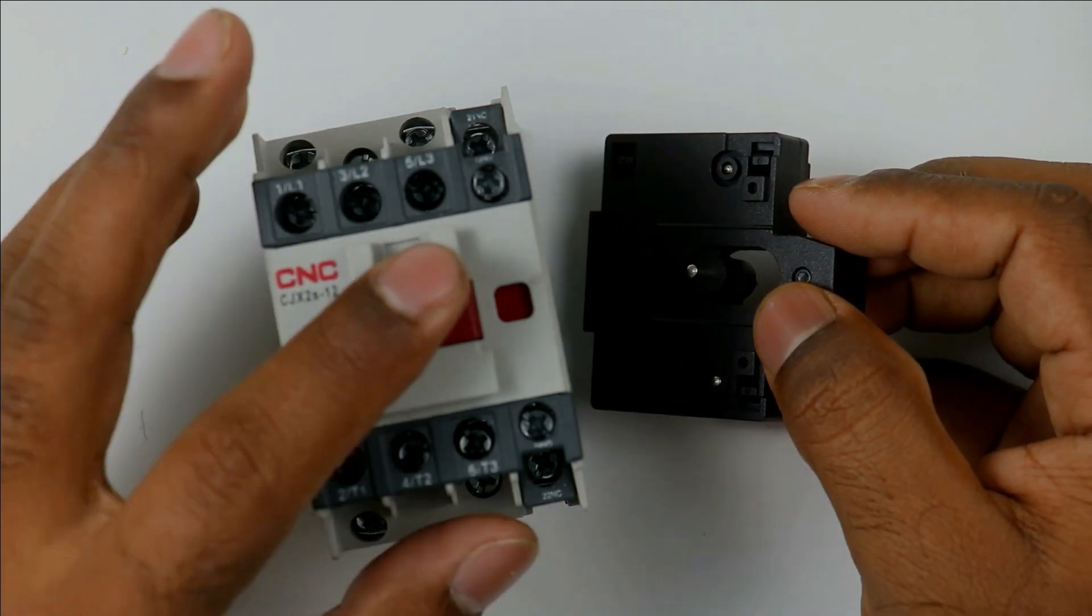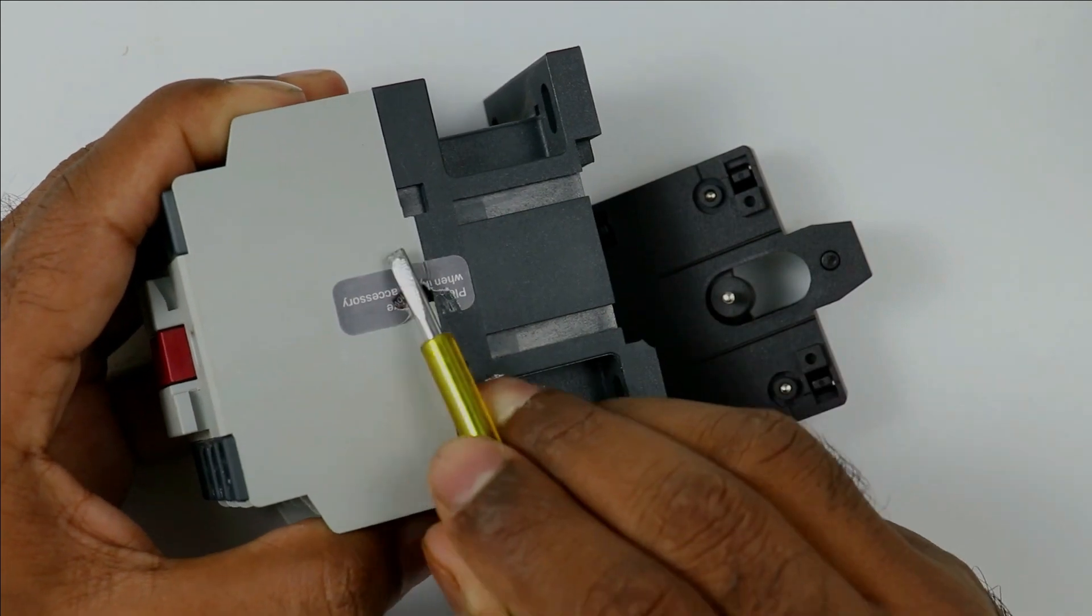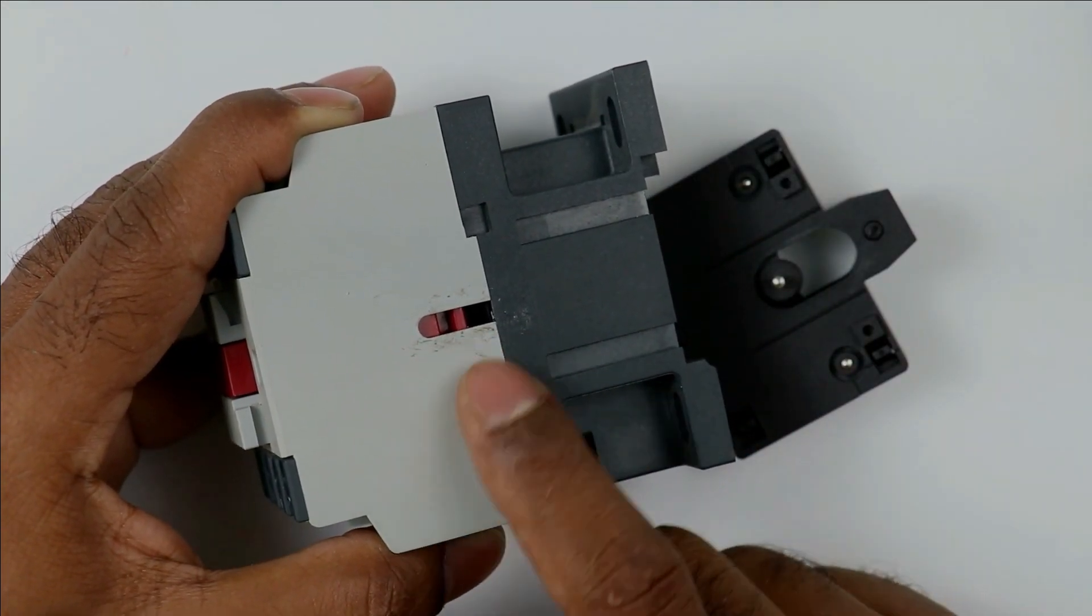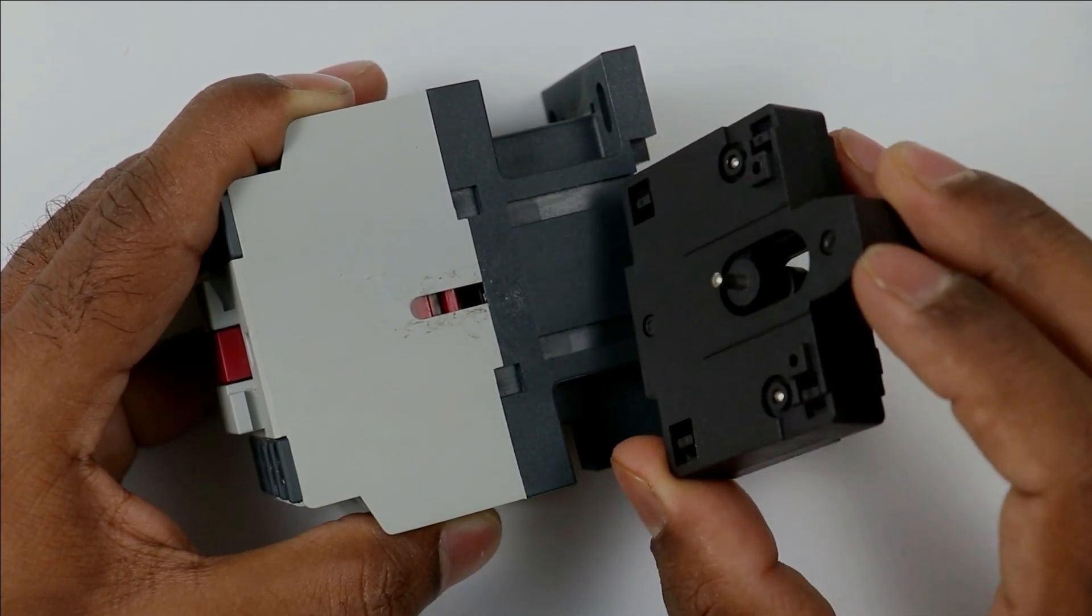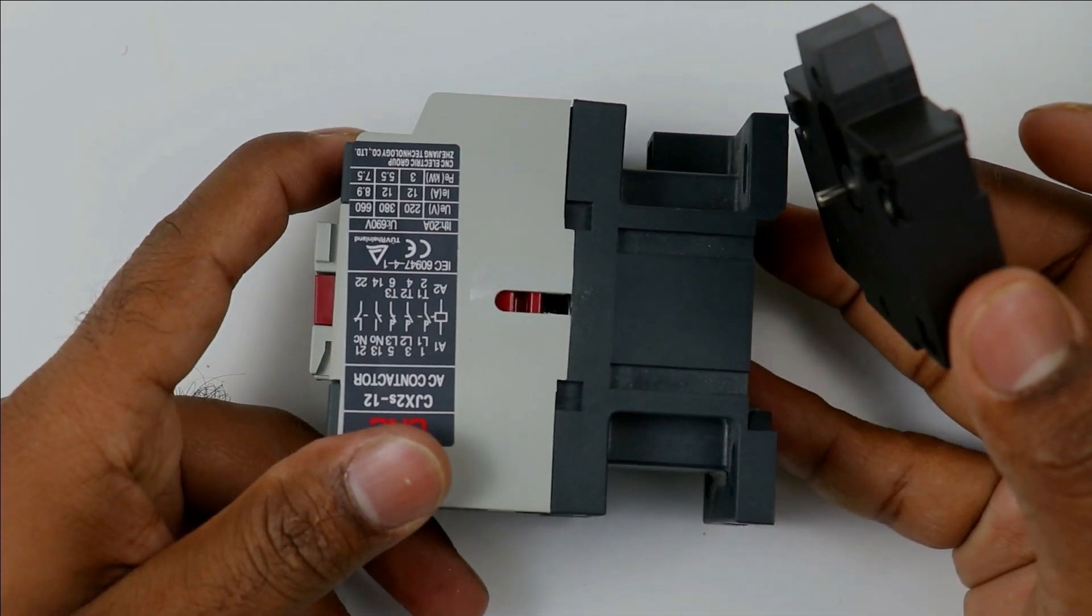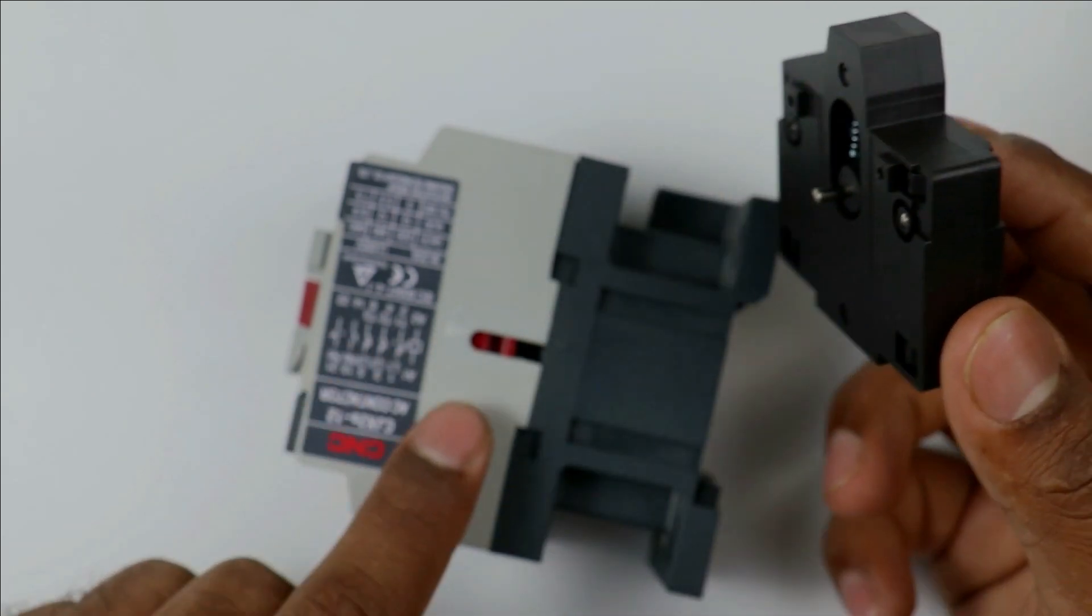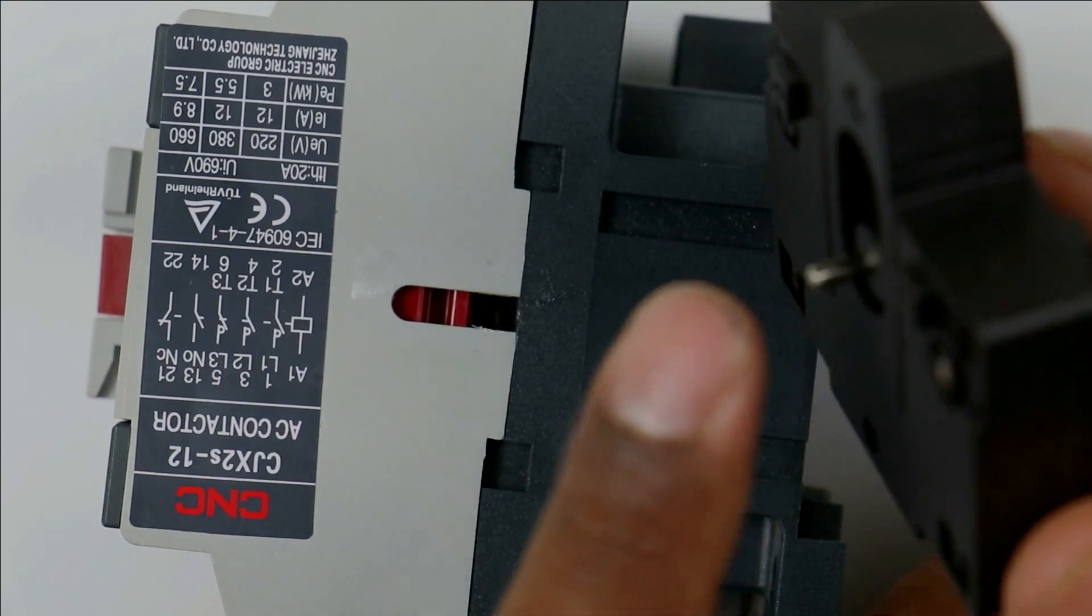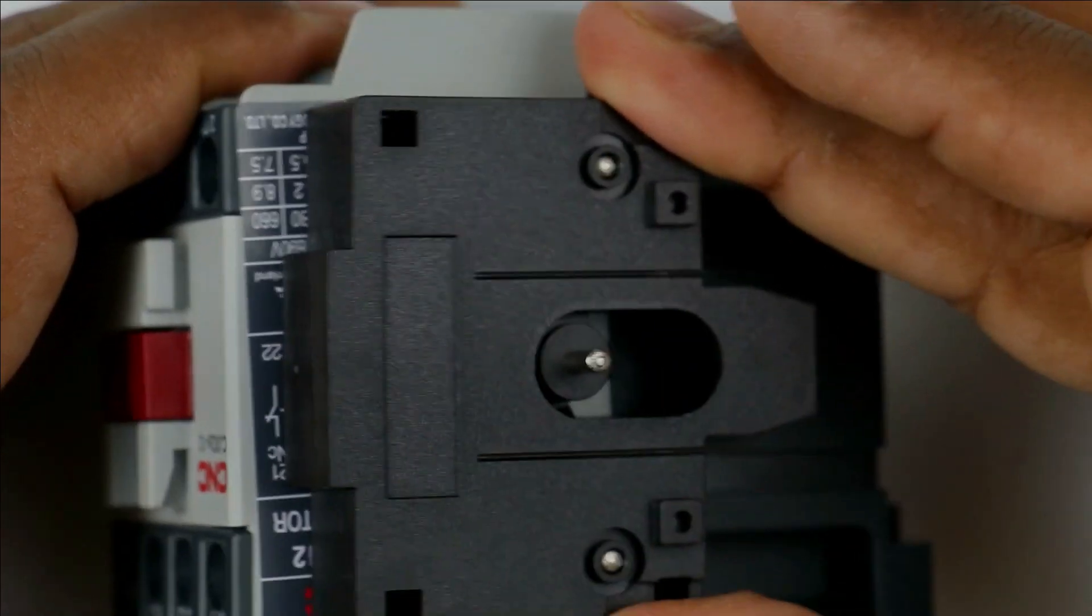In this contactor, if I look at this side, you can see a cover is there. First remove this cover. When you remove this, you will see something like this. Now we will have an option here to mount this contact. There is a simple way to mount this. What you have to do is place your contactor in this position. Now the contact you have has a knob. Take this knob and look at the middle of contactor. A slot is present there. You have to place this lever here. This has mounted perfectly.